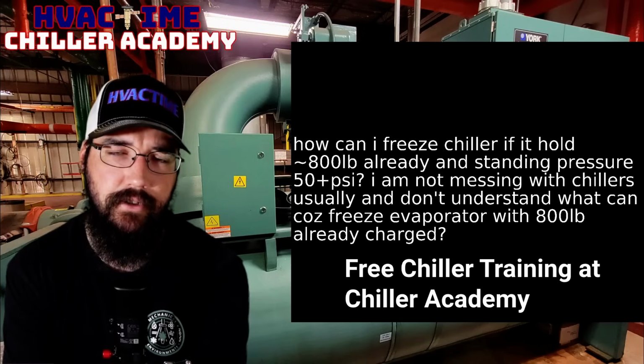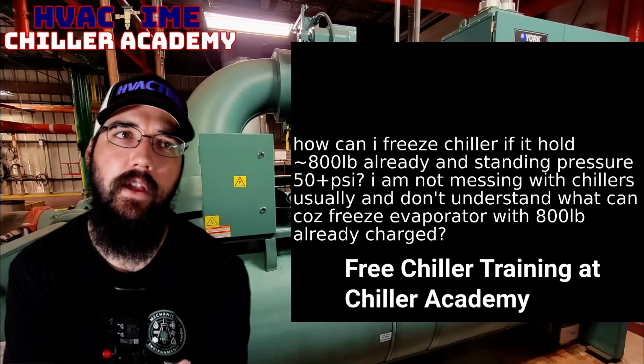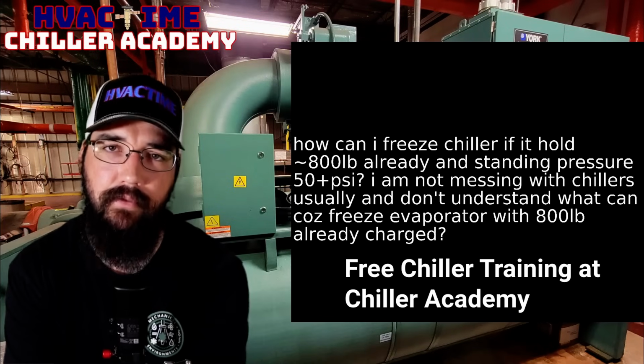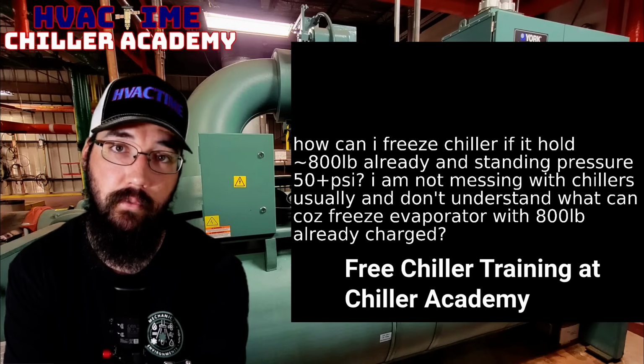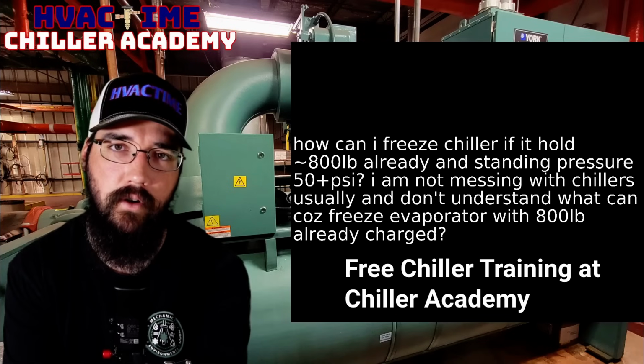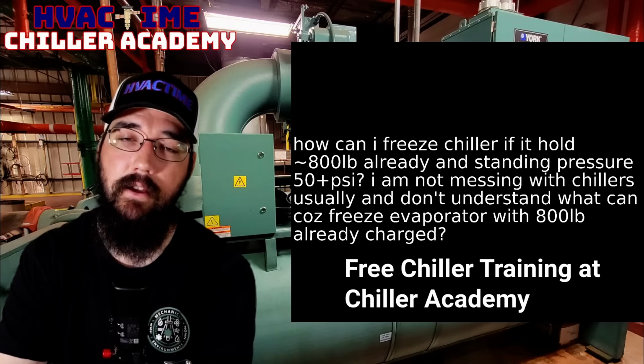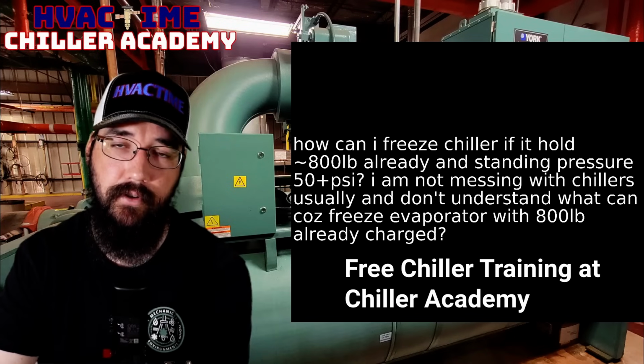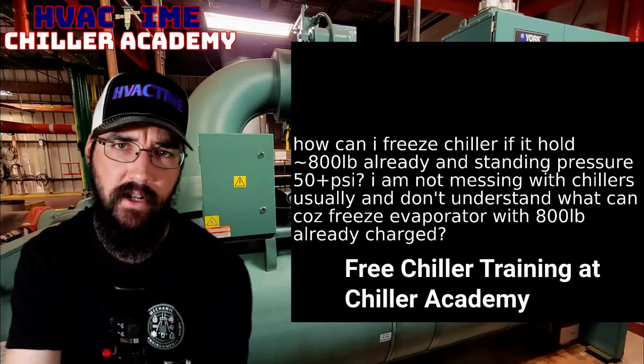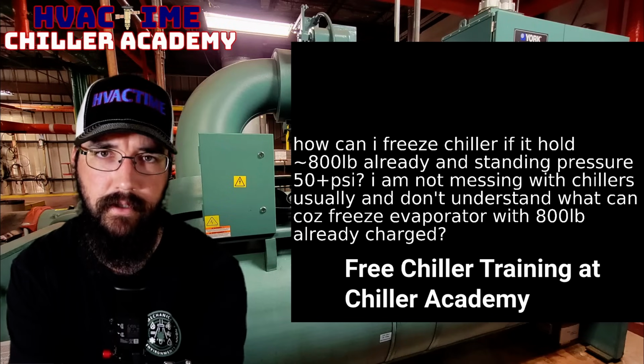With your standing pressure, if that is above your freezing saturation, then you're fine, because if your saturation is below freezing, then when liquid refrigerant specifically makes contact with the tubes with water in them, that liquid refrigerant can draw enough heat out of the tubes to freeze the water. Now, if our saturation, despite the refrigerant, is above a freezing temperature, then once that liquid refrigerant makes contact with the tube, we're not going to drop it below freezing to begin with. So we're not going to freeze that water, period. And that is the main concern.